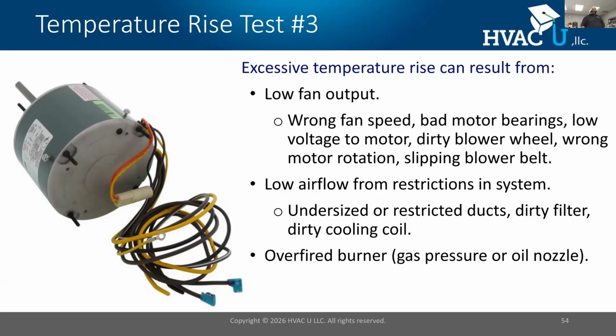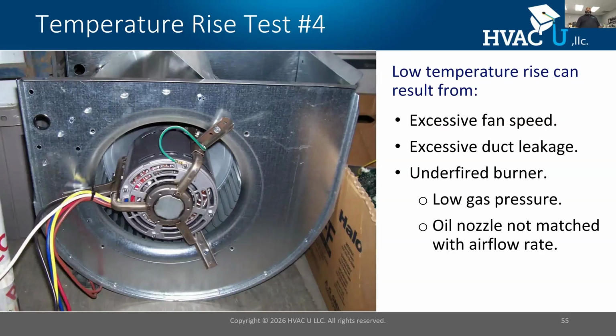It can also come from some neglect, maybe a dirty filter or dirty coil. Or it can come from an overfired situation, maybe I have too much gas pressure with the combustion appliance. When it's too low, that can be excessive fan speed, which is wasteful. Sometimes duct leakage can cause a low temperature rise. It can also come from underfire, where my gas pressure on my appliances or my nozzle pressure for oil isn't high enough, which is also a problem.